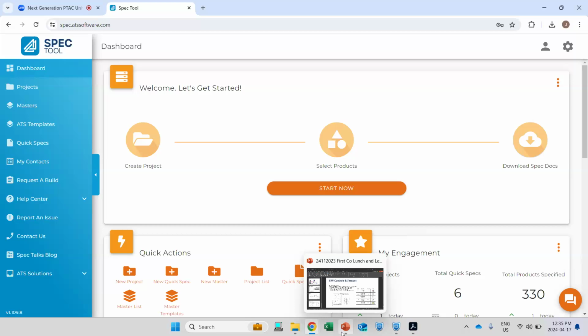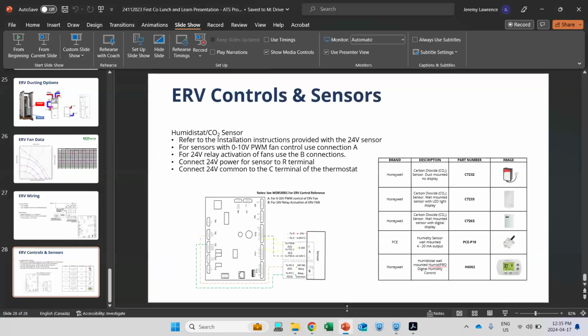It does, yeah. The defrost is controlled from within the unit, and it will control itself on and off based on its own measurements from the incoming air, and if it's required. Perfect. And then there's an additional couple of questions coming in here. You may have to do some interpretation for me. Sure. Do you have combined wall boxes for intake and exhaust, but must come from the manufacturer? I think that's a comment, maybe on some of the additional options that you showed, right?